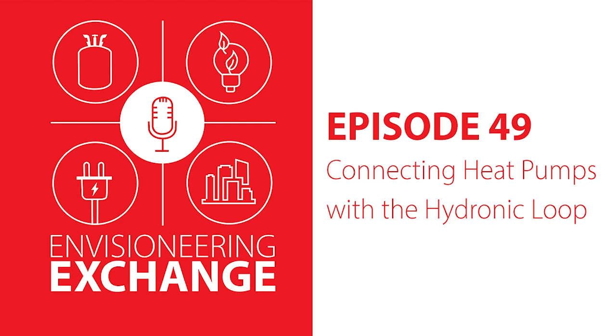And we see this especially in older buildings, like 10 years old or more. If you walk into the technical room and look at the temperatures going into the building and coming out, most of the time they are very small delta T's. So you know that there is a balance problem there. You know that there is maybe an overflow, or that maybe they even used the wrong system, because three-way valves used to be a thing.